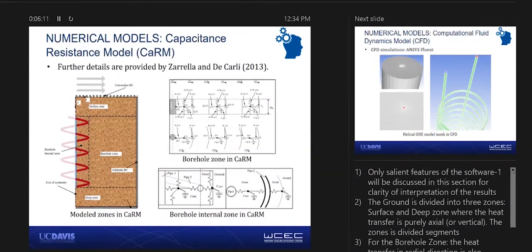The essential approach is dividing the entire region into zones. In the surface zone and the deep zone, you have heat transfer only in the axial direction, whereas in the soil internal borehole zone and the soil adjacent to the borehole, you have heat transfer in both the radial and axial direction. This is the resistance and capacitance diagram for that heat transfer.